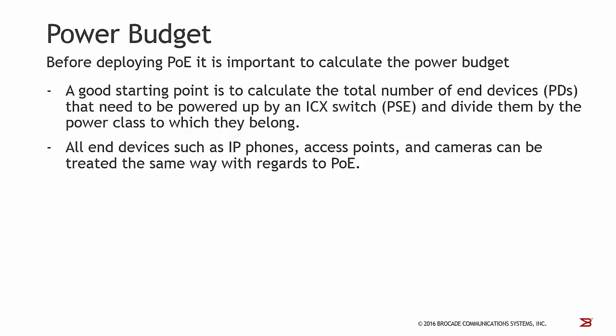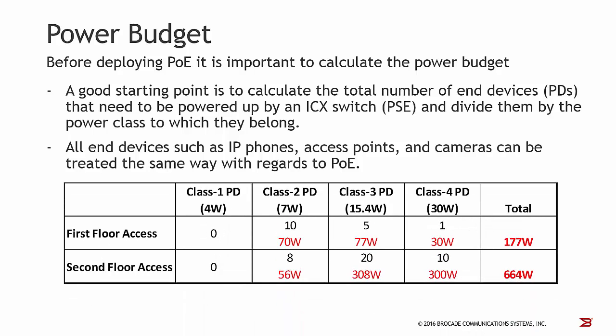Before deploying PoE, it is important to calculate the power budget, which is the power a switch can assign to all connected powered devices in parallel. A good starting point is to calculate the total number of PDs that need to be powered by an ICX switch and divide them by the power class to which they belong. All network devices such as IP phones, access points, and cameras can be treated the same way with regards to PoE. Here is an example for two floors where different devices consume different amounts of watts, and for each floor you calculate the total power needed to operate — that is the power budget the switches have to provide.